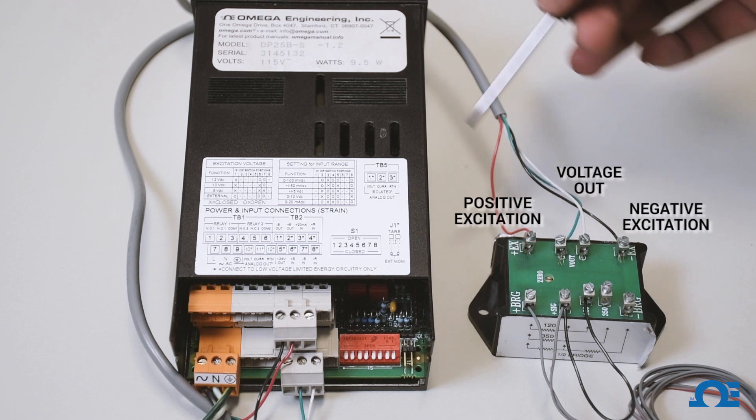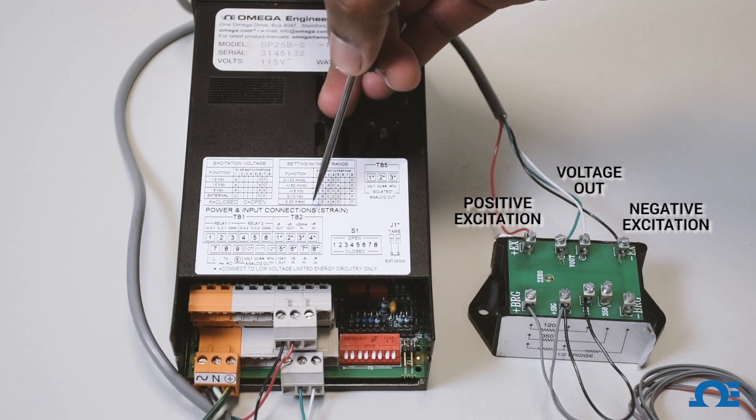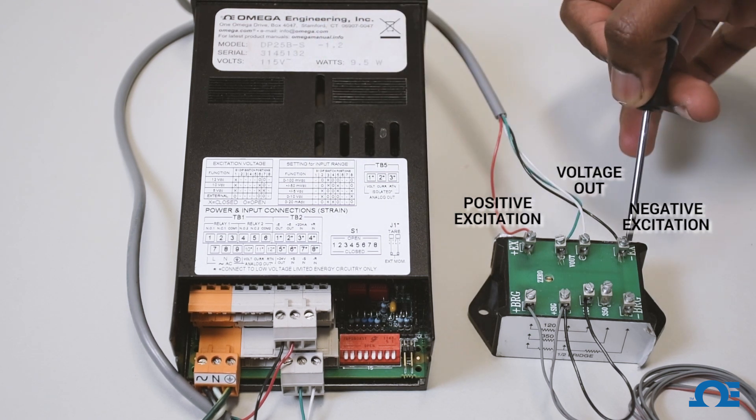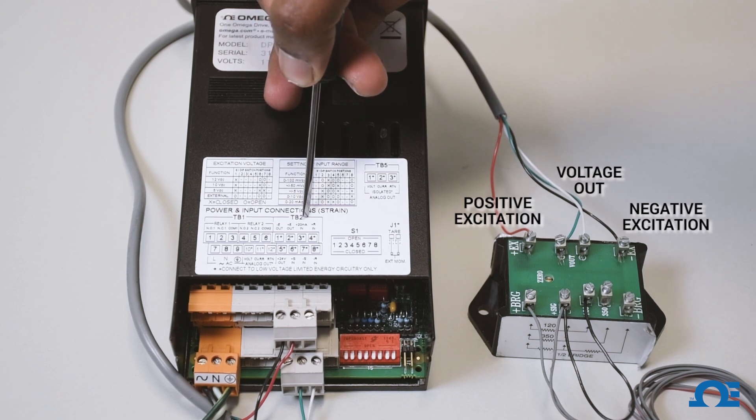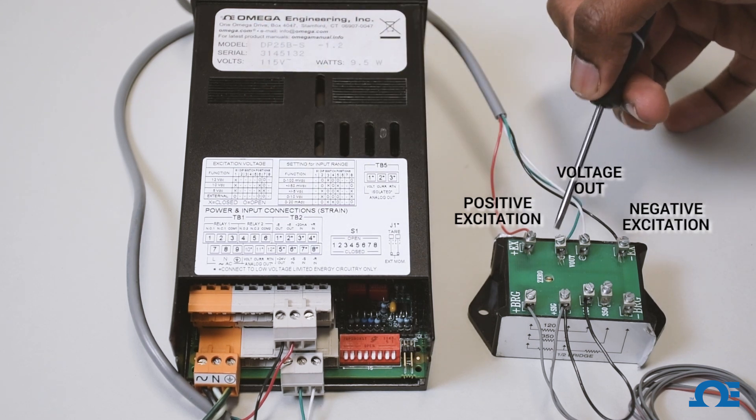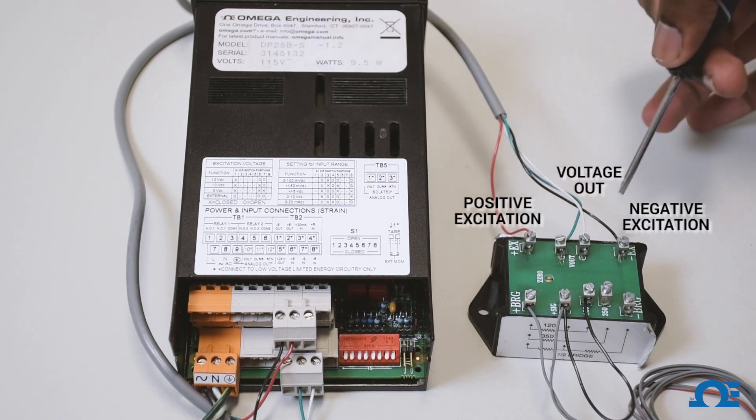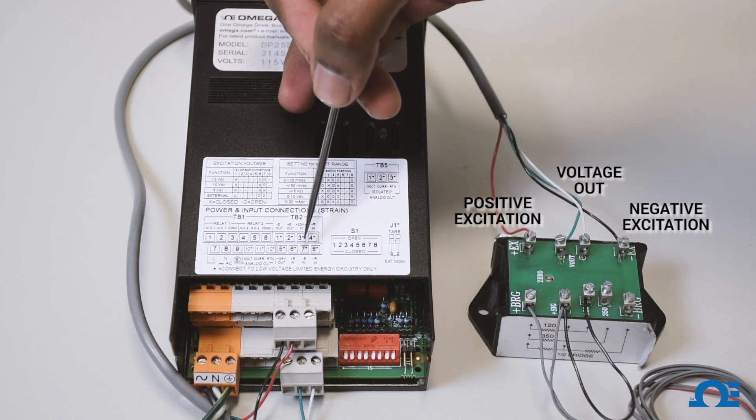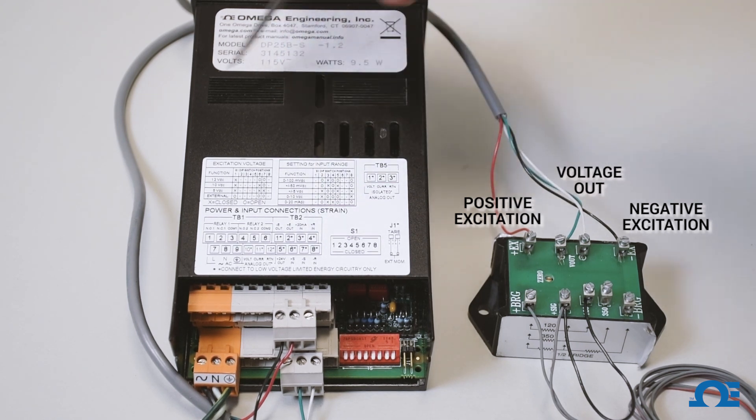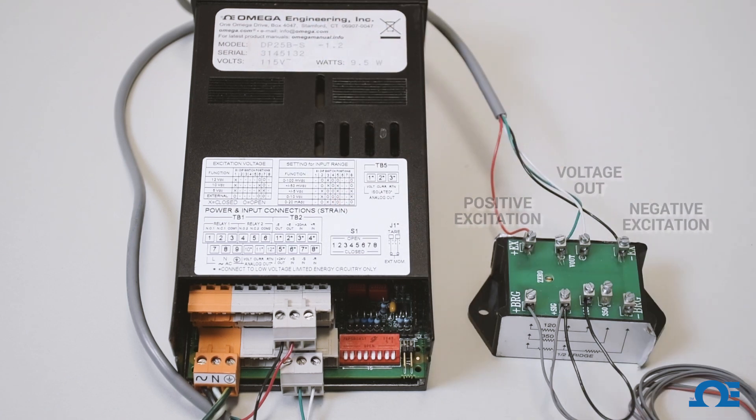Positive excitation connects to number 2 on TB2, negative excitation connects to number 1 on TB2, positive signal connects to number 6 on TB2, and negative signal connects to number 7 on TB2. That's how you connect a strain gauge to the BCM and the BCM module to the DP25B-S meter.